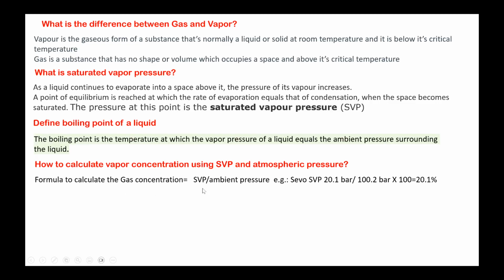The formula is saturated vapor pressure divided by ambient pressure. That is the formula you should use. For example, for sevoflurane, the saturated vapor pressure is 20.1 kPa and the atmospheric pressure is 100 kPa. So at 1 atmosphere, if we directly pour sevoflurane onto a patient's face, 20.1% sevoflurane will go to the patient. Okay, is it tolerable? Can any patient tolerate a 20% inhaled concentration of sevoflurane? No, sir. It will lead to toxicity, depressant to the cardiovascular system.